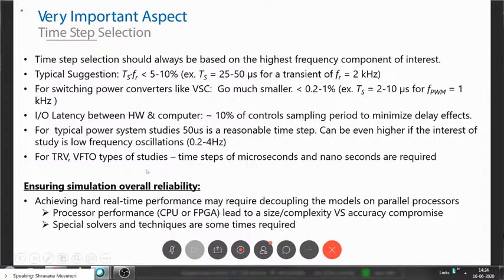One of the reasons for mentioning this in so much detail is these two points. Typically for power system studies, 50 microseconds is a reasonable time step, unless the interest is in much lower frequency oscillations, like the natural oscillations of 0.2 to 4 hertz, in which case you can go ahead and select milliseconds level. But typically 50 microseconds for instantaneous simulations of power systems is pretty good. But there are some exceptions as well.